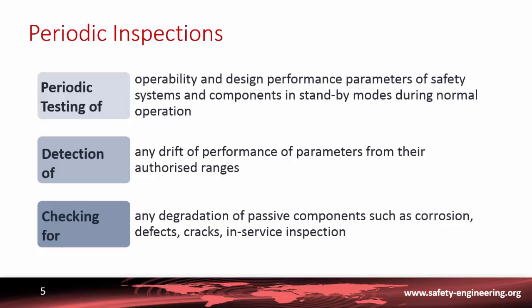Periodic inspection tests also serve to detect any drift in performance parameters from their authorized range — even if set points are complied with, any evolution of the parameters should be accounted for and corrections made. For passive systems and passive components, these periodic inspections also serve to detect any potential degradation by phenomena such as corrosion and cracks. This is what we call in-service inspection.